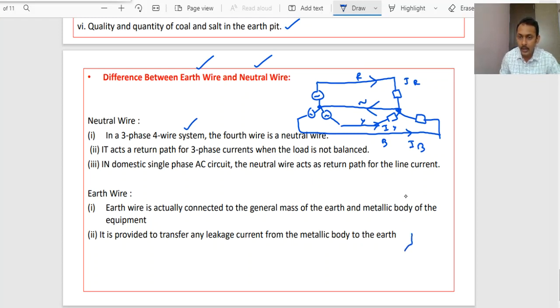Similarly, if you have a single-phase system where the load is connected, this acts like a phase wire, and with the help of the neutral wire the current returns. But what about this earth wire? If the system is solidly grounded, the neutral is earthed like this. This neutral point is earthed here. This is the neutral wire, this is the phase wire, and the earth wire is actually connected to the general mass of the earth and the metallic body of the equipment.